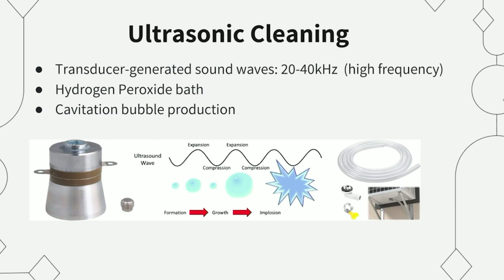Then in stage 2 is where our UV component comes in, and that's on a timer system with the Arduino as well. The reason we do a 2-component system is because it optimizes material use, which is essential in resource-limited settings. A little bit of the specifics: for our ultrasonic cleansing, we chose hydrogen peroxide as our solution due to its high affinity properties, and it's really easy to gain access to. The cavitation bubbles caused by the transducer target debris and other contaminants, which prepares our tools for the next step, which is the UV light.